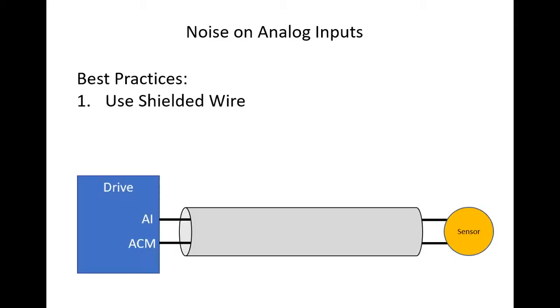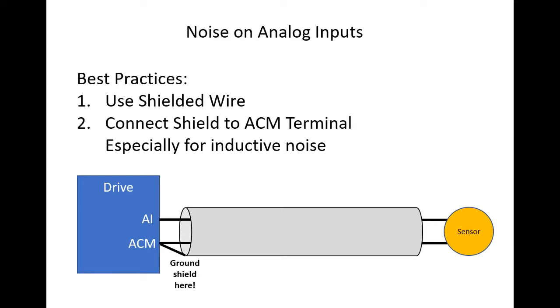Analog inputs can easily be affected by noise. The best practices are: use shielded wire, connect the shield to the ACM terminal, especially if the noise is from an inductive source. Grounding the shield at the drive end is all you need. Don't ground the other end of the shield because you can create a current loop that will just create more noise.